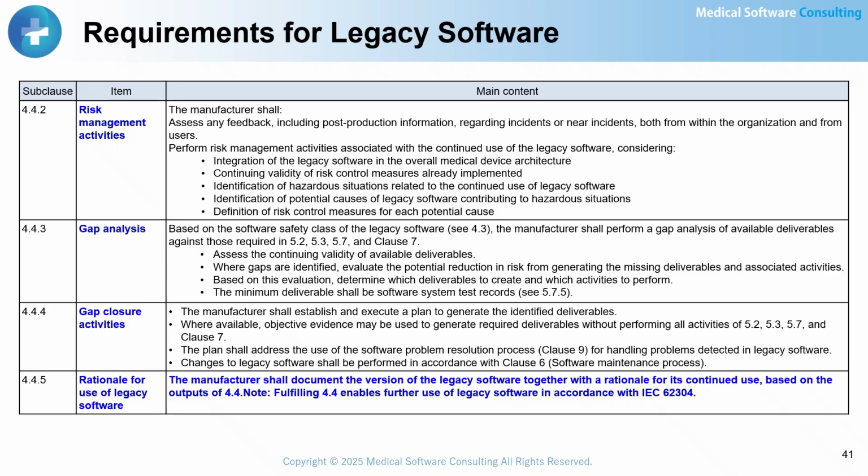The requirements for legacy software are as follows. Clause 4.4.2, Risk Management Activities. Manufacturers must evaluate all feedback related to legacy software, including internal and external post-production information on incidents or near incidents.